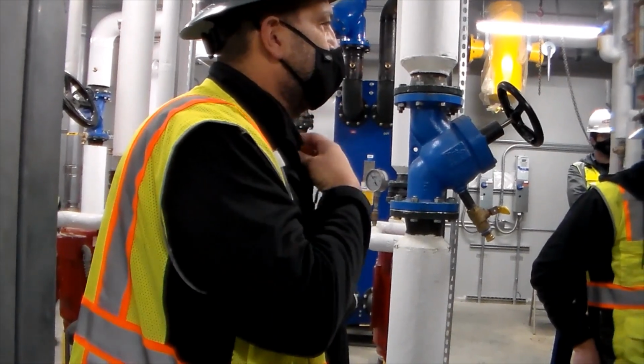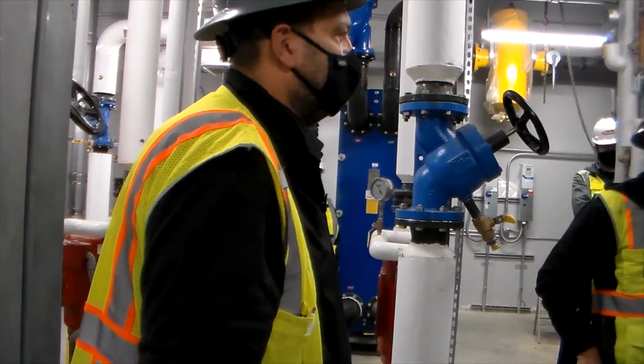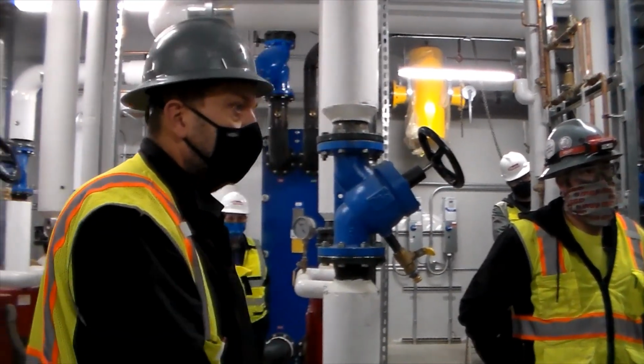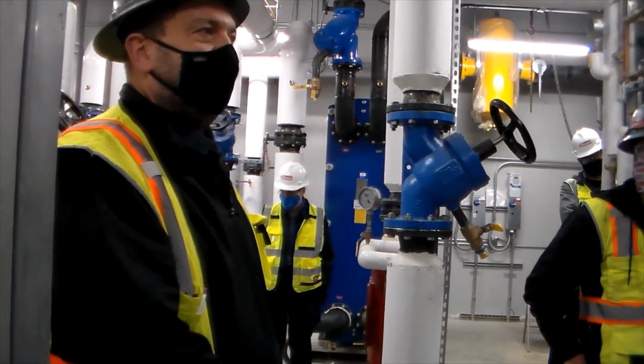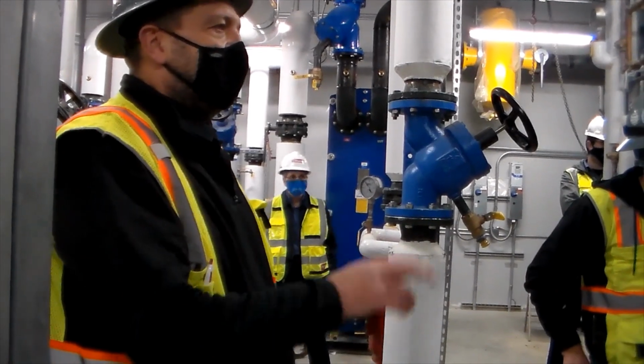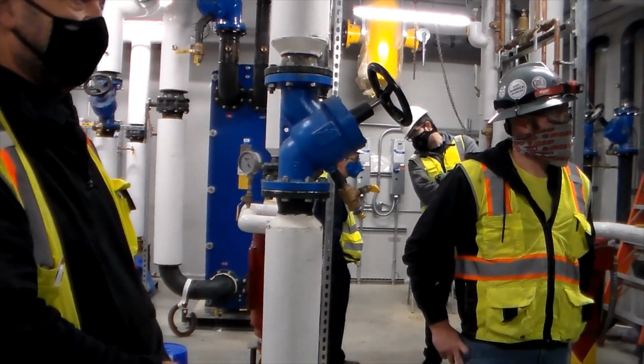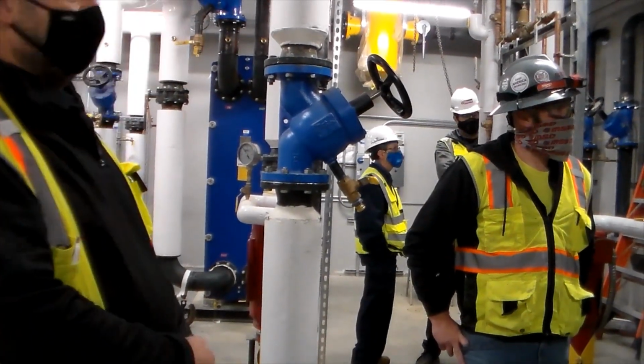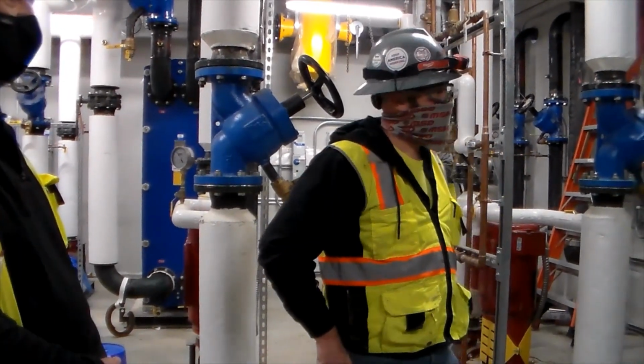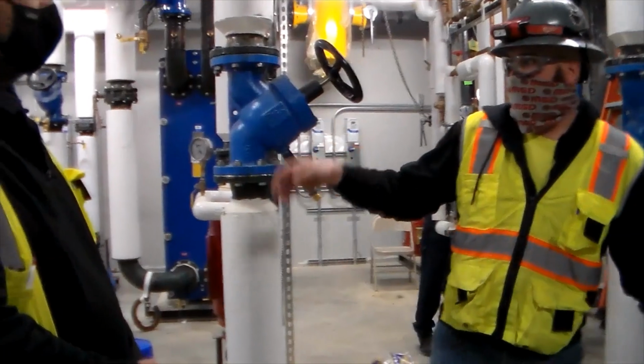Will that bring up a boiler alarm if it fails, or no? If the pump fails, it will bring an alarm. Yes. And what's the capacity here? How many pumps will it take to run us at 70% building capacity? I have not the slightest idea. We want to know if we need all 3 to stay open. This is sized so that it'll feed 66% of the entire thing. So we're 2/3. Right. Okay. Same temperature. It might be a little cooler, but we'll be all right. Okay, got it. All right, I guess we'll get a little bit deeper into the room.